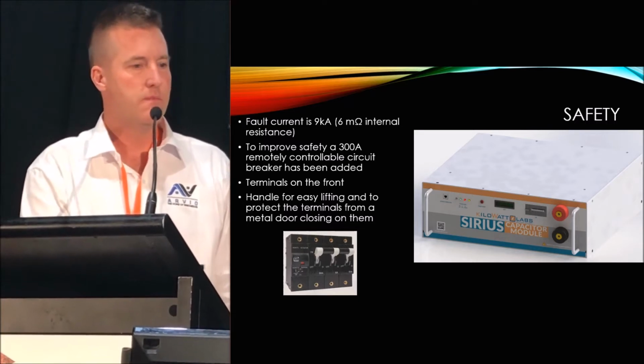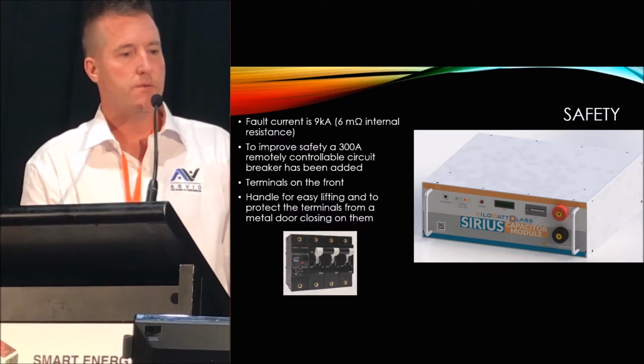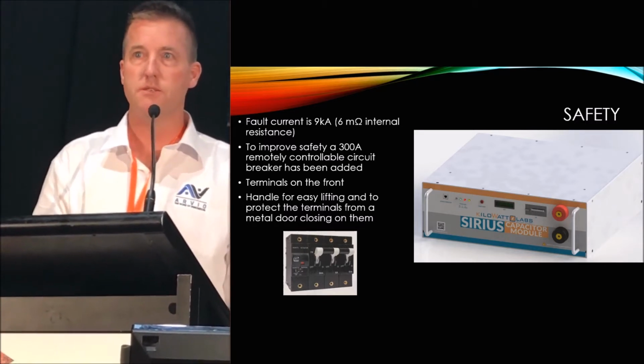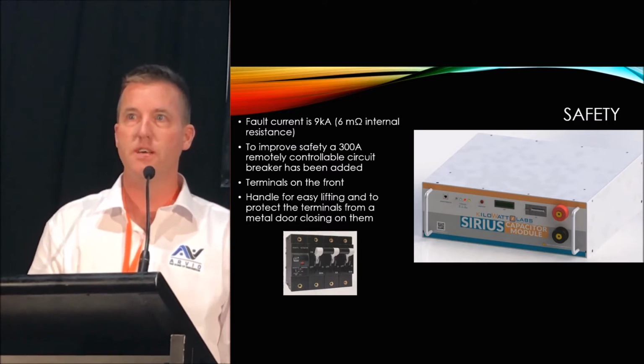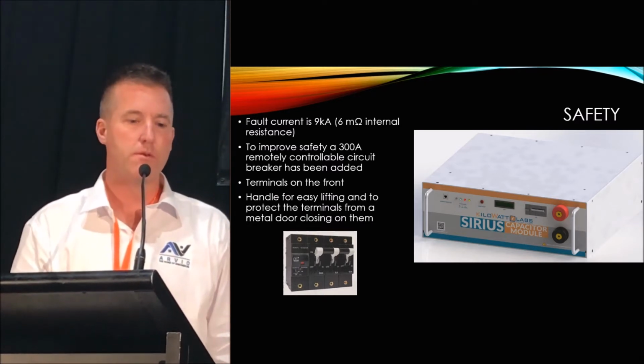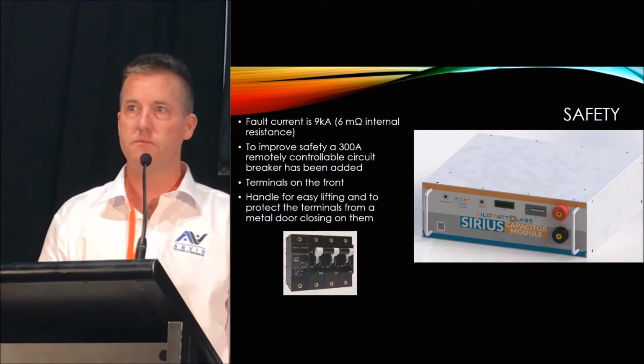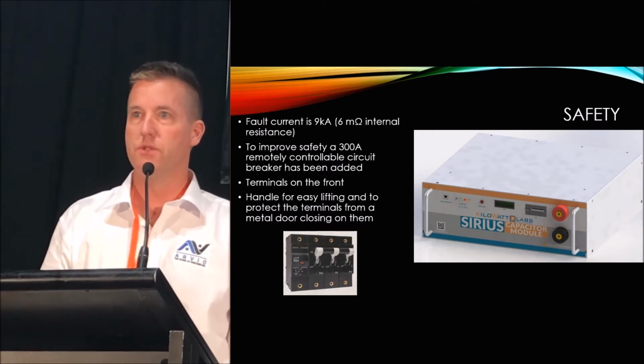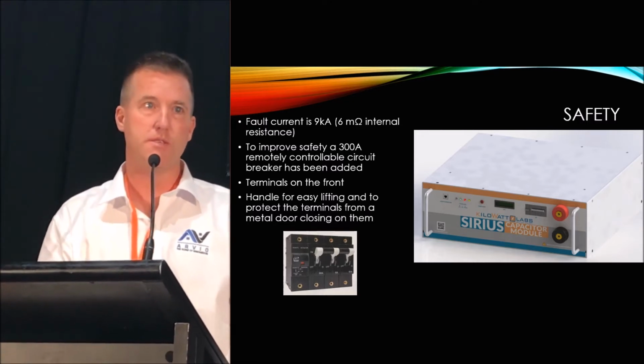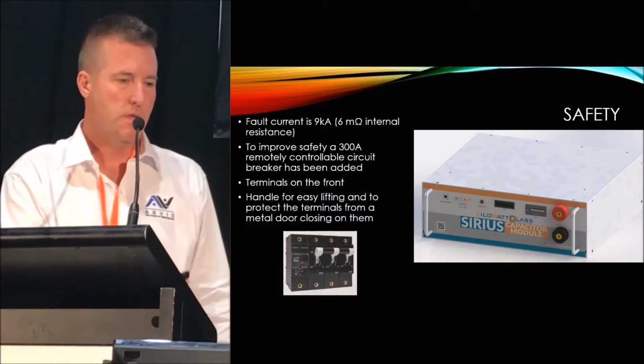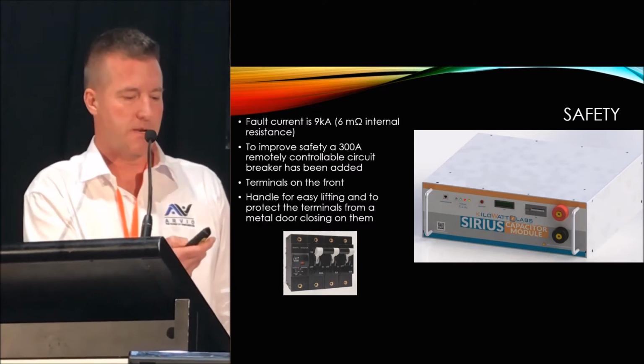It's quite useful. It's got a very low internal resistance, which means a very high release of energy. If you dropped a spanner across the terminals with no circuit breaker in there, the energy release is so high it could almost vaporize a piece of metal. So the circuit breaker helps protect against that.